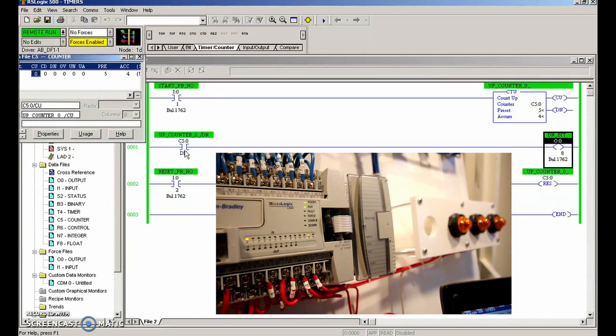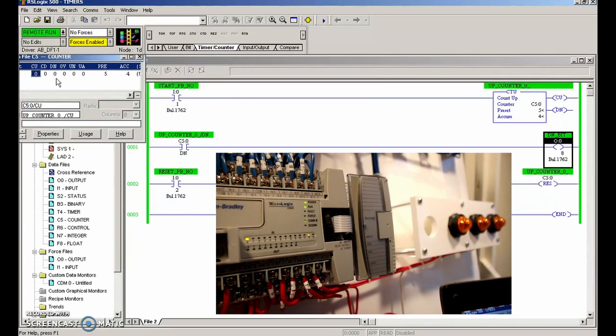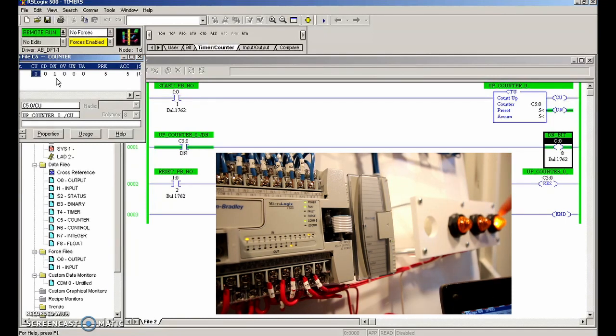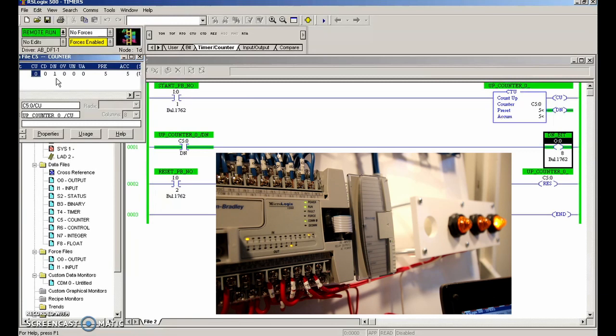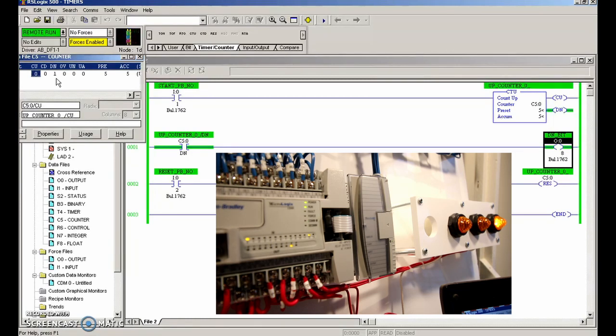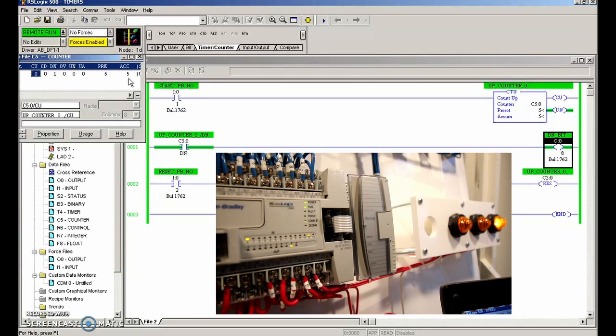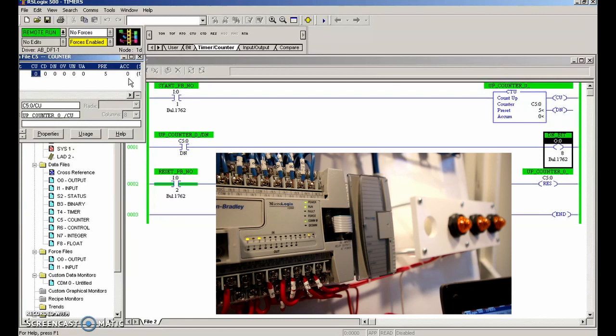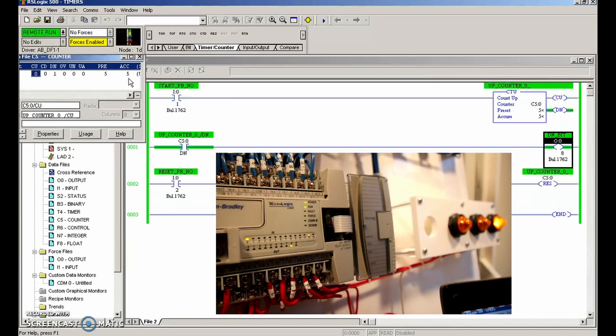We're looking at the done bit for when it goes from a zero to a one. When it goes from zero to one we're going to turn on our first indicator light. Going from four to five - the done bit sets. As soon as the accumulated value is equal to the preset, the done bit is set and our indicator light has turned on. As soon as I hit the reset button, the accumulated value goes right back down to zero, the done bit is no longer true, and the light turns off.